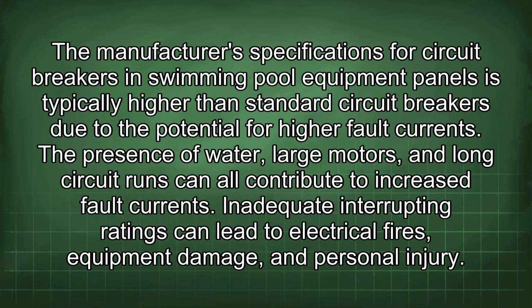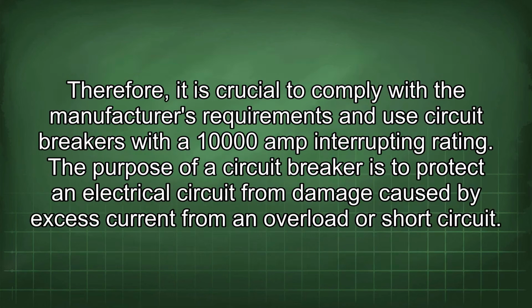The manufacturer's specification for circuit breakers in swimming pool equipment panels is typically higher than for standard circuit breakers due to the potential for higher fault currents. The presence of water, large motors, and long circuit runs can all contribute to increased fault currents. Inadequate interrupting ratings can lead to electrical fires, equipment damage, and personal injury. Therefore, it is crucial to comply with the manufacturer's requirements and use circuit breakers with a 10,000 amp interrupting rating.